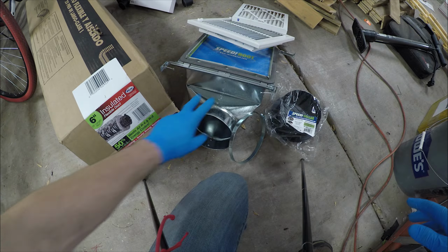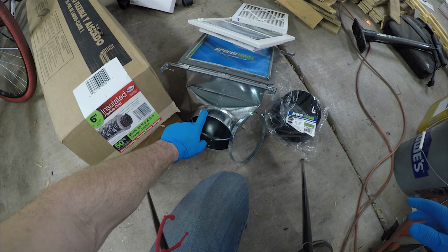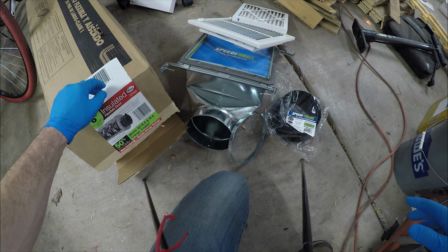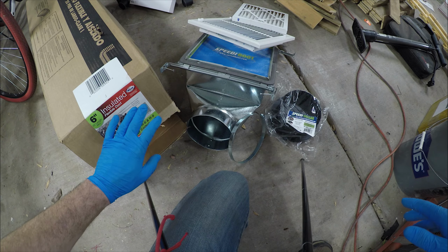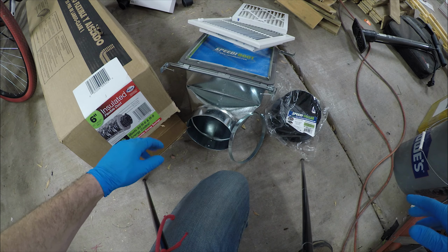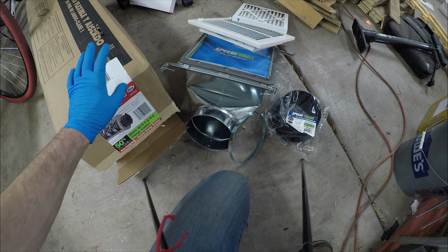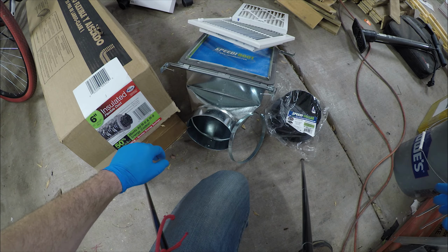You'll also need insulated flexible duct. In this case, I've got 6-inch duct to match the 6-inch boot connection, and this is the more heavily insulated variety. They make a cheap version that has a thin layer of insulation and a more expensive version, I believe it's R8 here, that has even thicker insulation, so it'll do better in terms of energy savings. Again, a little more expensive than the cheap variety, but definitely going to save you money in the long run.